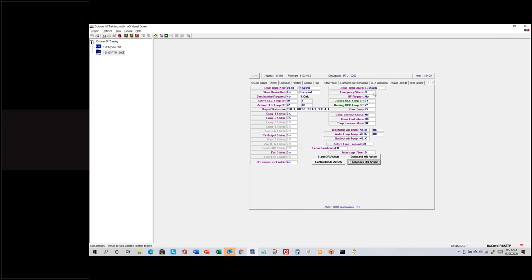I'll go higher to 77. It needs to be more than a degree and a half to exceed the one-degree setting — that's why I now have a low alarm. I'm about 2.2 degrees below set point. The same thing happens on the high side: if the temperature is above the cooling set point by more than the zone temp alarm range, you get a high temperature alarm.